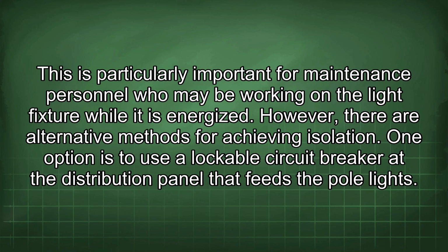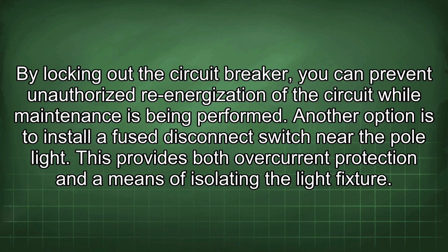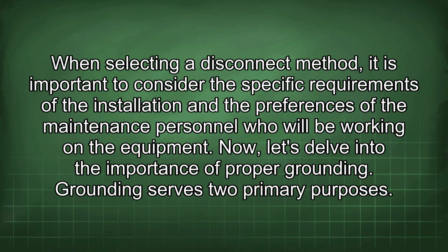One option is to use a lockable circuit breaker at the distribution panel that feeds the pole lights. By locking out the circuit breaker, you can prevent unauthorized re-energization of the circuit while maintenance is being performed. Another option is to install a fused disconnect switch near the pole light. This provides both overcurrent protection and a means of isolating the light fixture. When selecting a disconnect method, it is important to consider the specific requirements of the installation and the preferences of the maintenance personnel who will be working on the equipment.